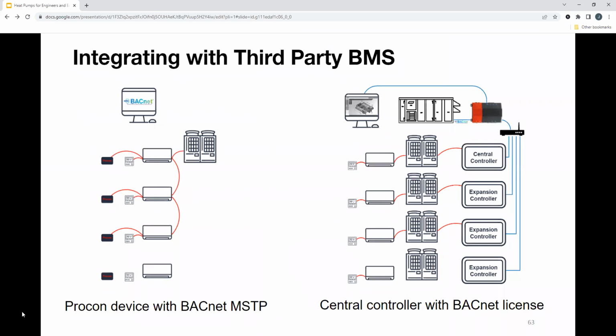And this is what it looks like. This would be your Procon with the MSTP, right? You have your local controllers with the condenser, and then you have this Procon device that's wired to BACnet. And then the central controller would tie this large system together, right? And then you can add, and this would then go to the BMS that would take care of a rooftop unit or what have you.